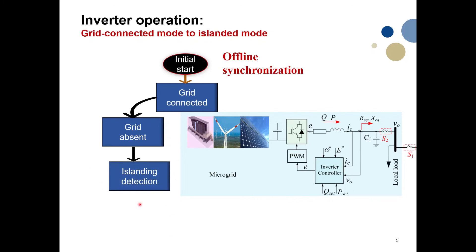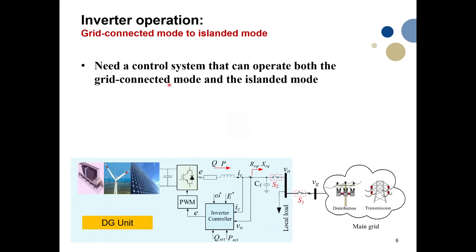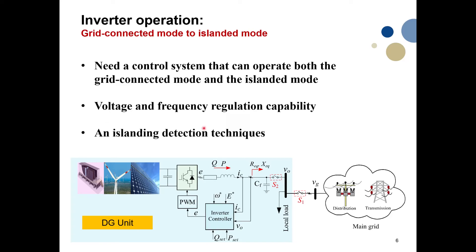When islanding is detected, the inverter operates in islanded mode. So we need a controller that can operate in both grid-connected mode and islanded mode. In islanded mode, since no other generation is present apart from this distributed generation unit, the controller needs voltage and frequency regulation capability to control frequency within the desired range. The islanding detection technique must accurately detect islanding without causing disturbances and within a reasonable time — according to standards, within two seconds.